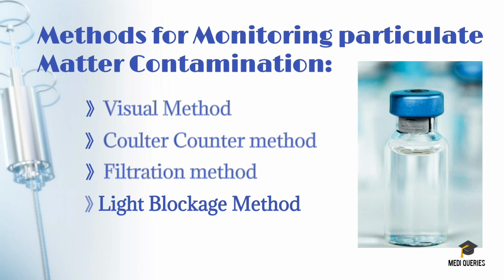The method gives an automatic evaluation of the particles in hydraulic fluids. It allows a stream of the fluid under test to pass through a bright white light source and a photodiode sensor. It is possible to detect the cross-sectional area of the particles in this instrument because the particle blocks the path of the light, and the size of the particle is considered as the diameter of a circle of equivalent area. So this is another type of method.